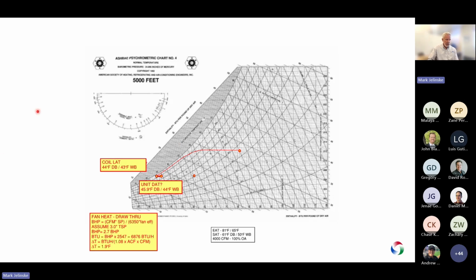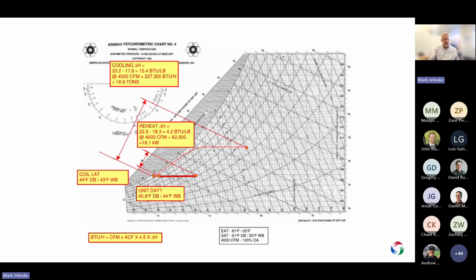This is probably going to be a draw through unit. By the way, another critical condition that we were given was that this needs to be a less expensive, packaged unit. So I know that it's probably going to be a draw through unit because of that. That's going to add fan heat, and you can see my numbers here. It adds about 2 degrees of heat, and it slides over to the right there. But we're still too cold, aren't we? The airstream needs to be heated up.